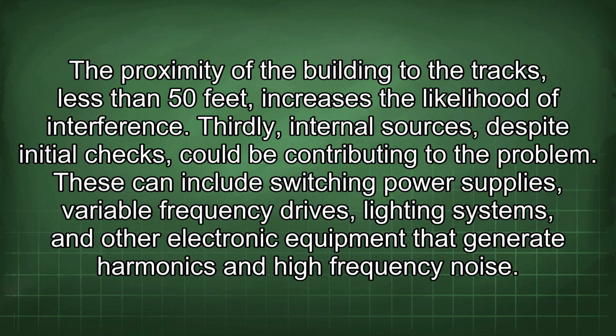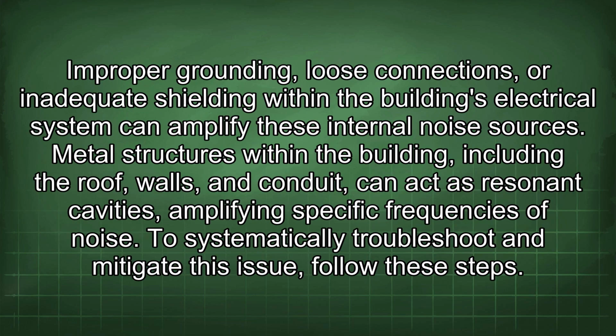Thirdly, internal sources, despite initial checks, could be contributing to the problem. These can include switching power supplies, variable frequency drives, lighting systems, and other electronic equipment that generate harmonics and high-frequency noise. Improper grounding, loose connections, or inadequate shielding within the building's electrical system can amplify these internal noise sources. Metal structures within the building, including the roof, walls, and conduit, can act as resonant cavities, amplifying specific frequencies of noise. To systematically troubleshoot and mitigate this issue, follow these steps.